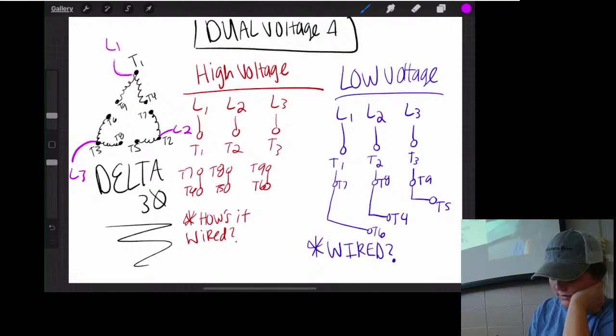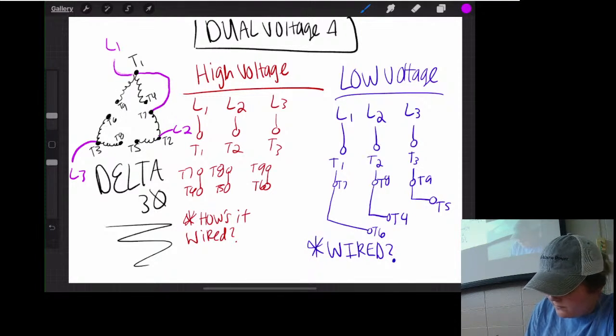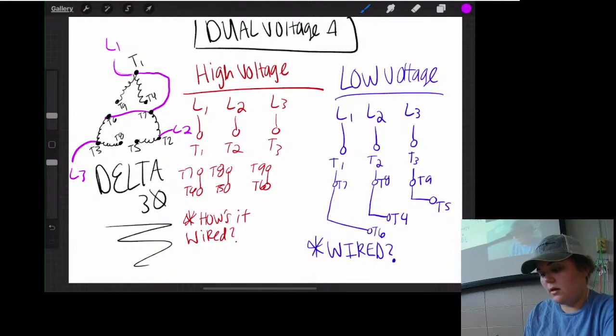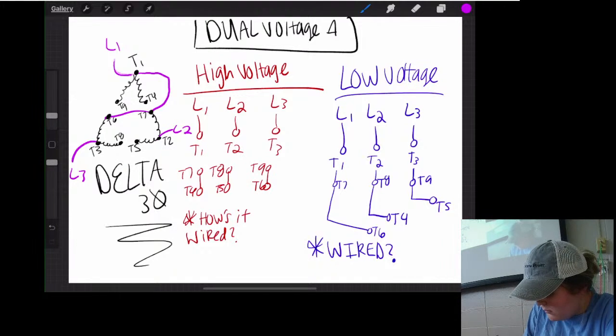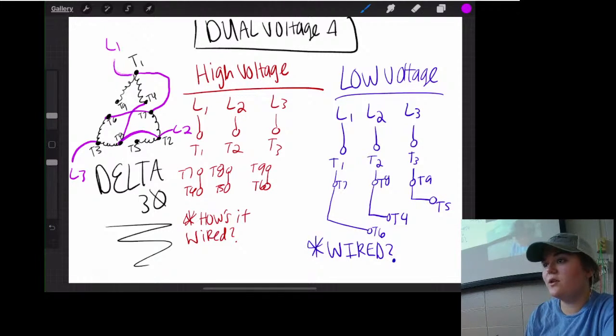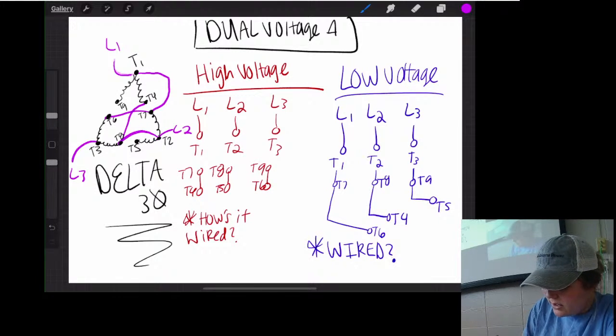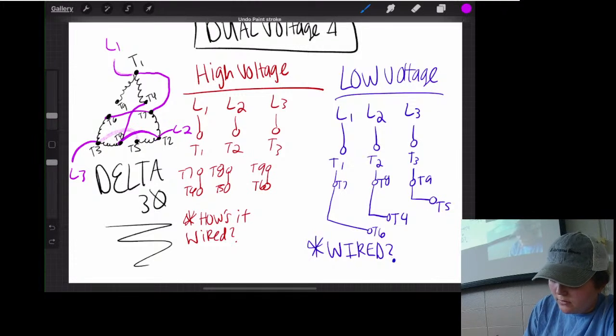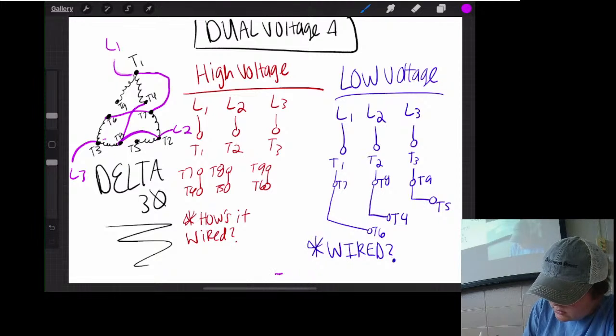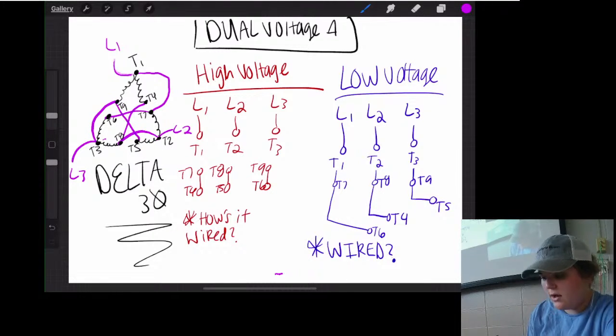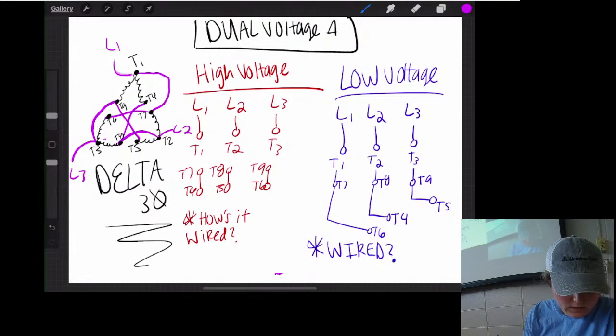And then it's going to go to T6. Let me make sure I'm not telling you wrong... yep, okay, so they're all connected. This is going to bounce around to T7, and then it's going to go to T6. And then we're going to have T2, wherever it might be, over on the right side. It's going to bounce over to T8, which is in turn going to bounce over to T4. And I know this looks really confusing, like super confusing. And then T3... is going to bounce over to T5. Dang it, I was going... T9, T3 to T9 and then. You're right, sorry, you're right, T3 bounces over to T9, and that bounces down to T5. This just looks like a whole lot of craziness because I'm not as good at drawing it as the book is, but that is how you'd wire up a delta in parallel.